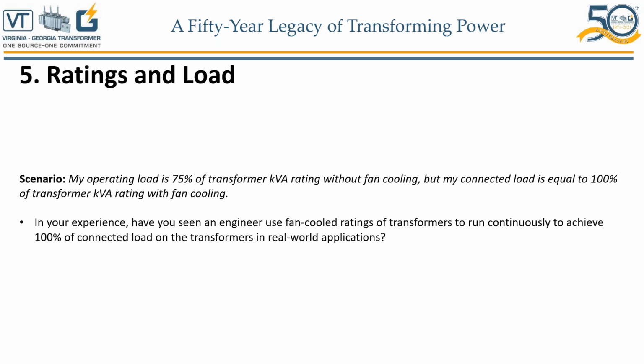And as I said in my previous webinars, the reason why 95 is that we want to keep everything below 100. We don't want to get past 100 and start degrading the insulation, because then the tiny amounts of moisture in the insulation will start breaking down. So having said that, here the question is talking about fan cooling. Can I run it at 100?